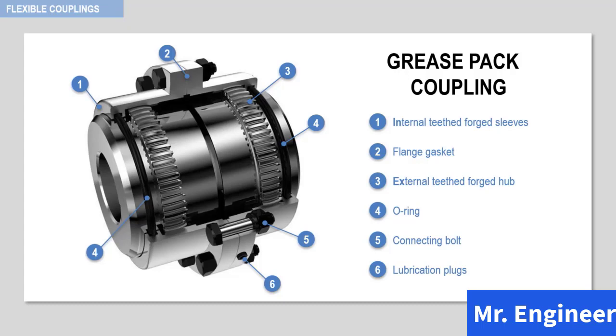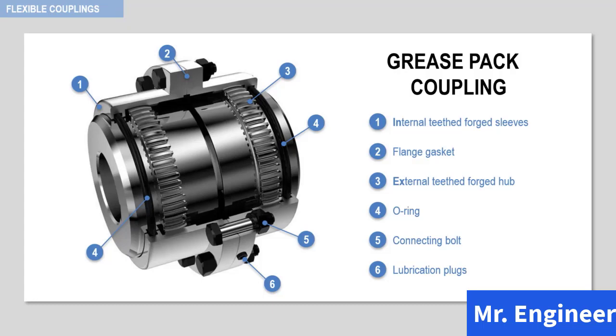In recent years, flexible element couplings have been used almost exclusively. However, many gear type couplings are still in use. They are the most compact coupling for a given amount of torque transmission of all the coupling designs, and for this reason they also have the least overhung weight. In addition, the gear coupling can adapt more readily to requirements for axial growth of the driver and driven shafts. Axial position change tolerances are on the order of one-half inch or greater.